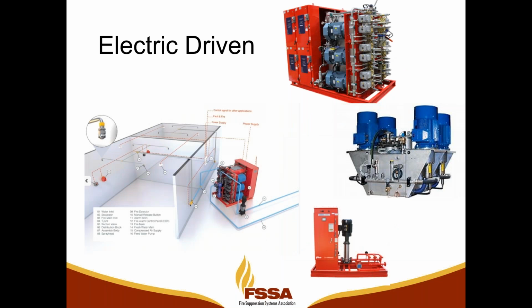Then you also have electric-driven pumps. Electric-driven pumps come in all shapes and sizes, both low pressure and high pressure. The advantage of electric pumps is as long as you have electricity and a source of water, you'll be able to run these pumps infinitely. You can stop and start them as you need them to be available. Once you stop them after an event, they'll be ready for the next event right after you stop the pump the first time. So if you have multiple fires in an industrial type application where you're deploying water mist, for example, like an oil cooker or something to that effect, these type of pumps would be easily resettable and ready for the next event, should a fire happen on another piece of machinery or the same piece of machinery that had the fire in the first place.